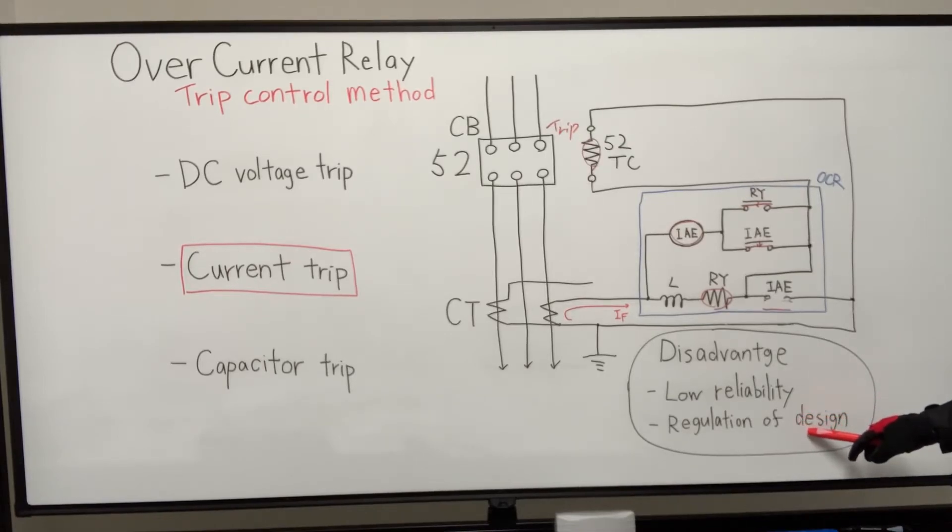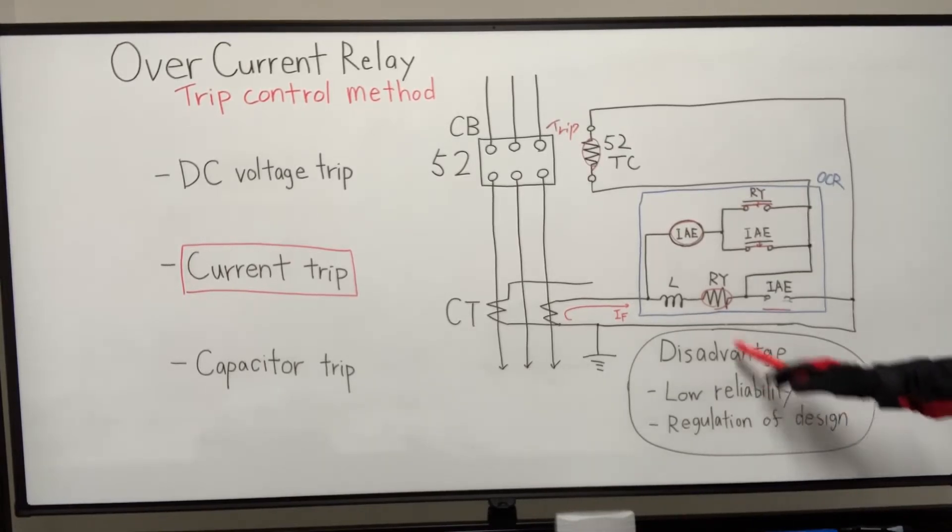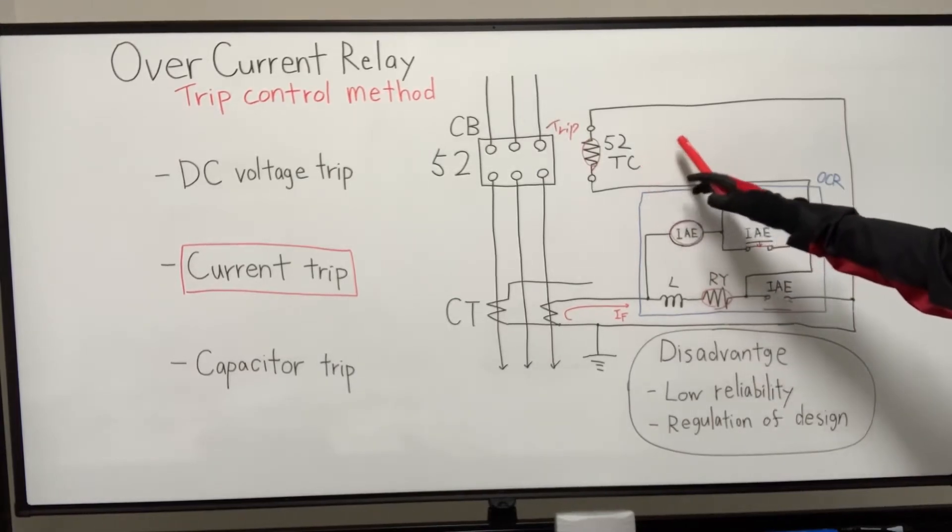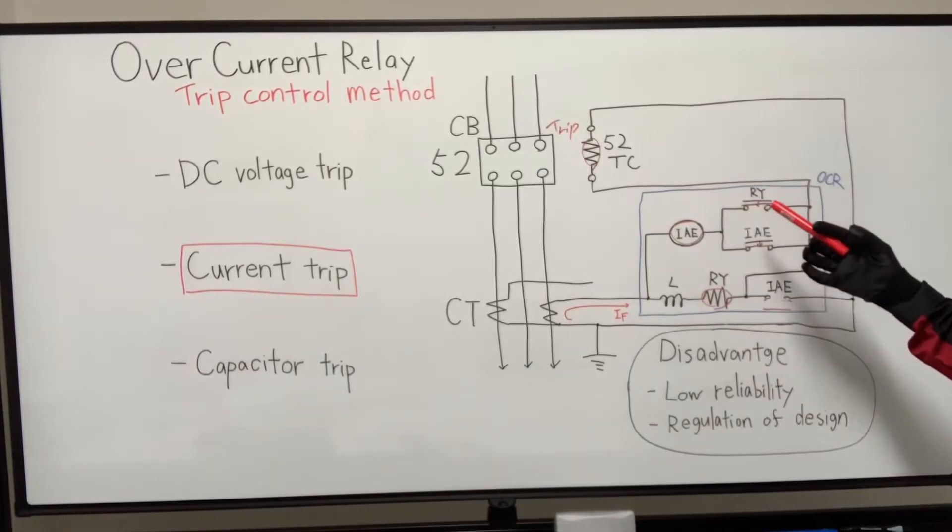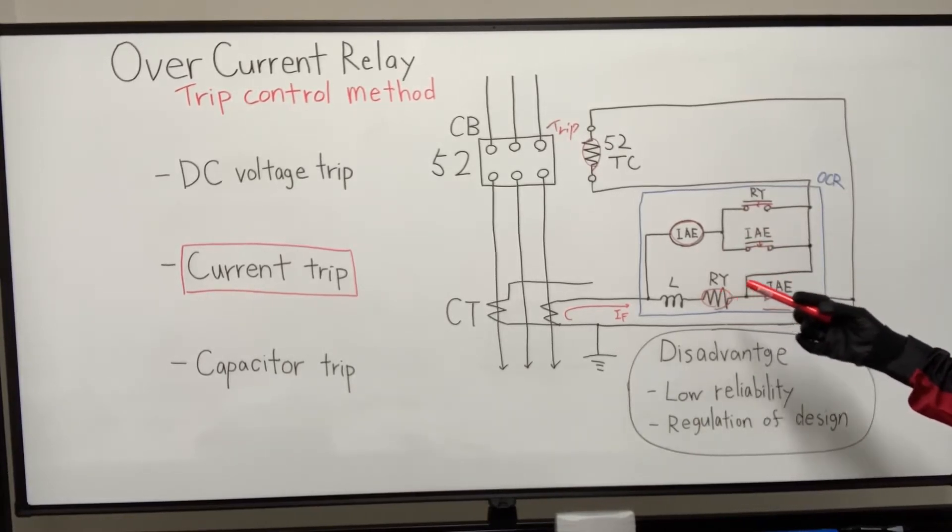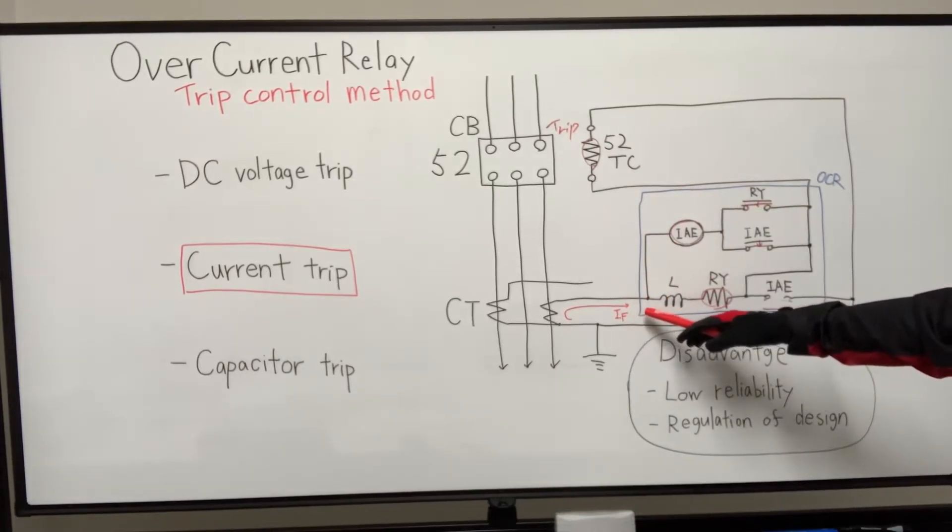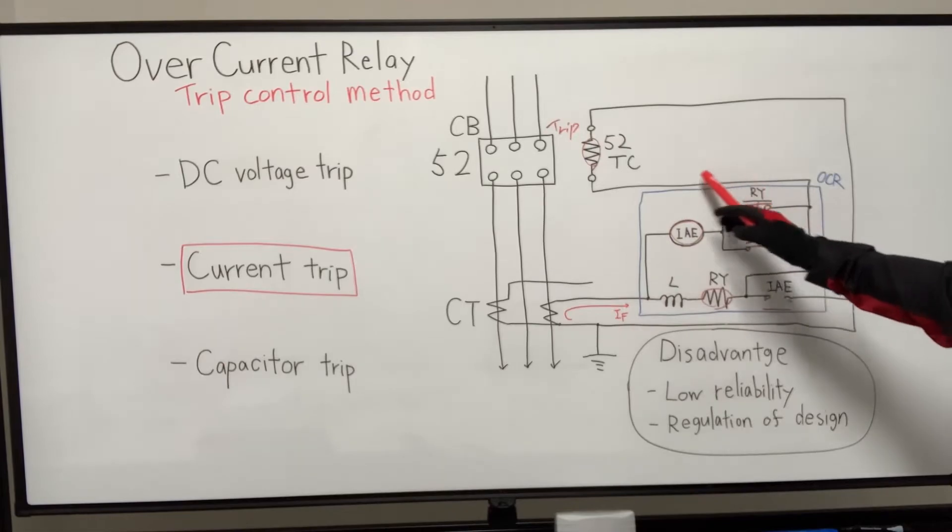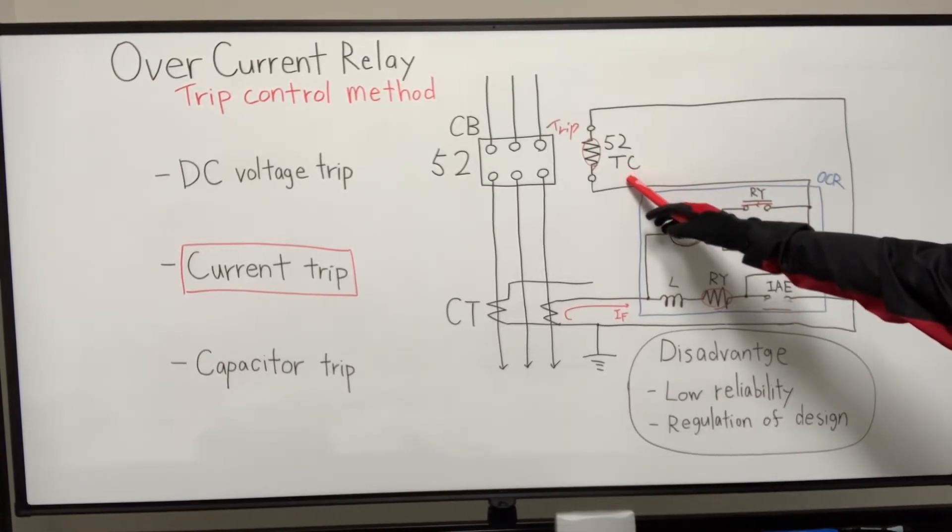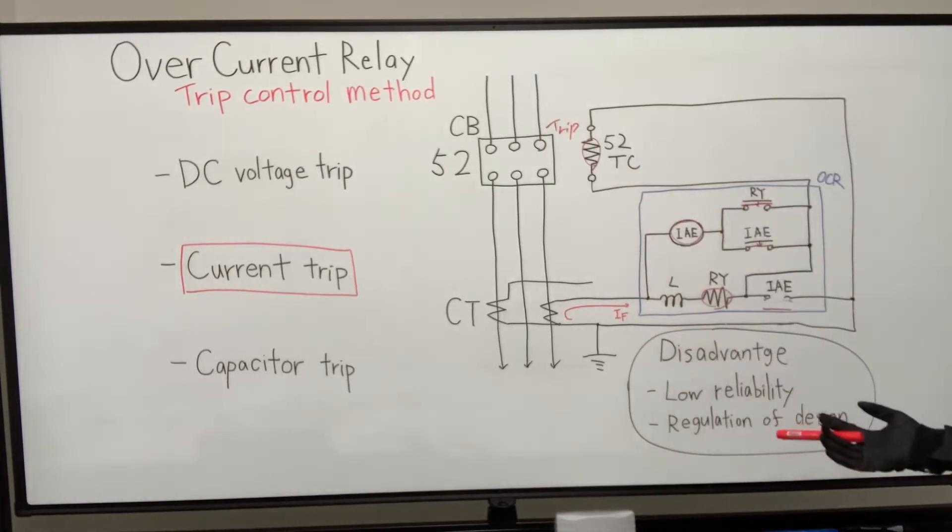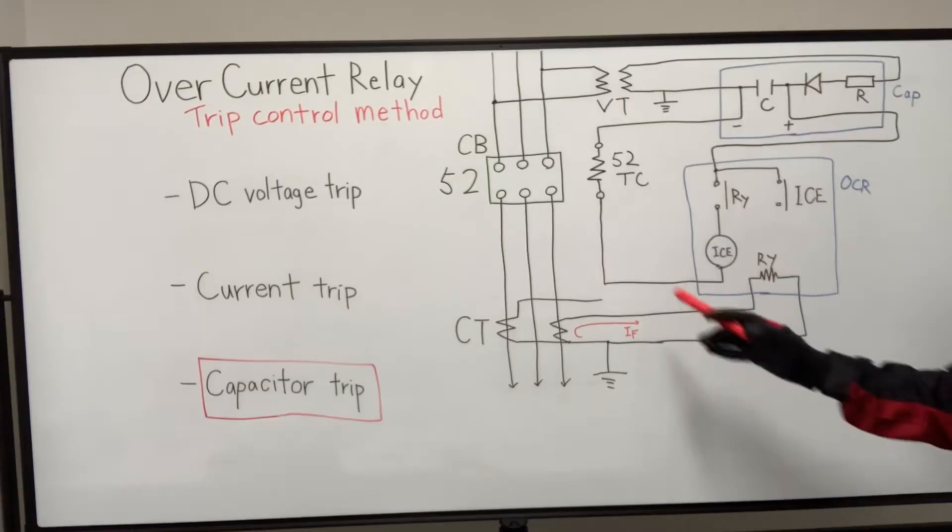And also, we need to take into account the trip coil has a minimum operating current value. And the CT secondary current should be greater than this minimum operating current. So it's kind of a regulation of designing. So we need to consider it. So I think it's sort of a disadvantage.